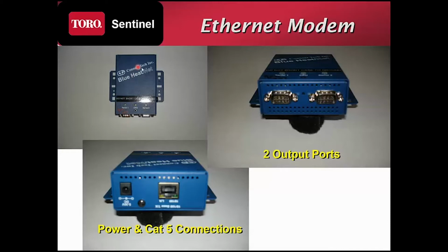If you wanted to go to a weather station, say a Davis weather station console, the back end of that IP address, 192.168.42.10, would have :10002, and it would transmit over serial 2. So it allowed you to get double access to devices out of one piece of hardware and one IP address. So the IT department did not have to provide 2 Ethernet drops right there.